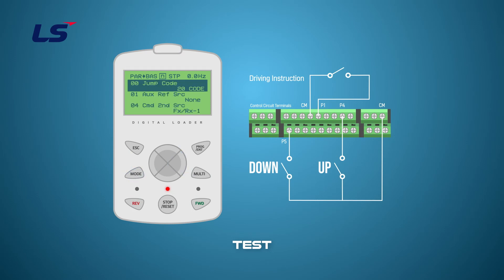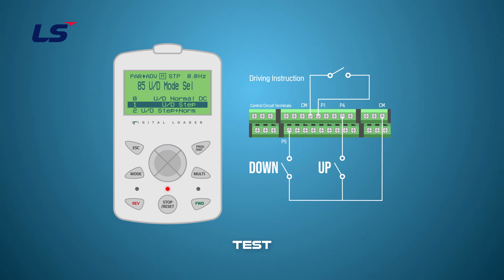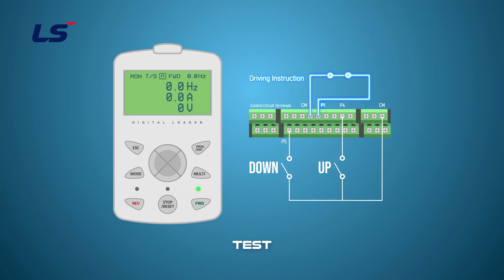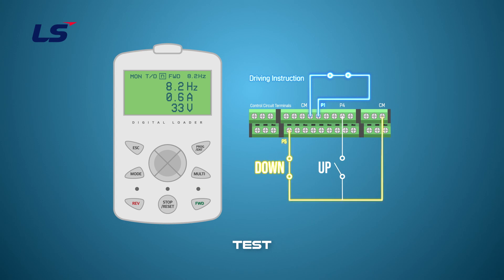Next, let's test the Up-Down step operation. Change the Up-Down mode of ADV 85 to 1 while maintaining the previous test settings. Then set the Up and Down step frequency of ADV 86 to 5 Hz. After setting this, initiate the FX digital input by turning it on, then turn on the digital input programmed as Up and wait. It can be seen that although the Up digital input is still on, it accelerates by 5 Hz set as the step frequency and then no longer increases. If you turn the digital input programmed as Up off and on, you can see that it rises 5 Hz again to reach 10 Hz. If the Down is turned on, it decelerates by the step frequency.